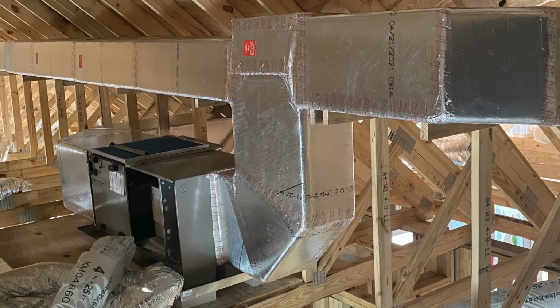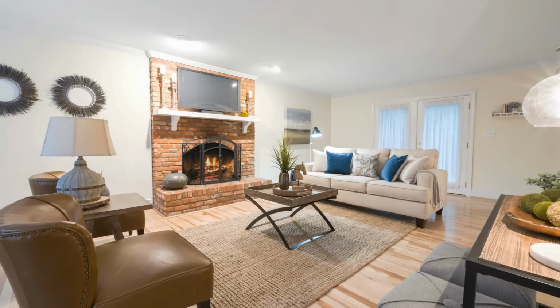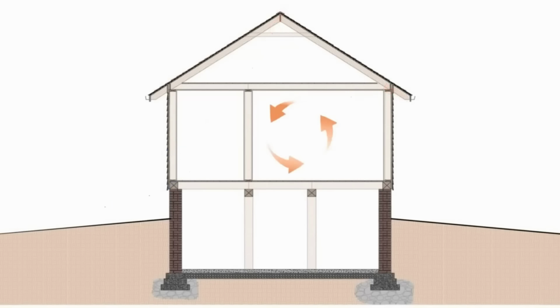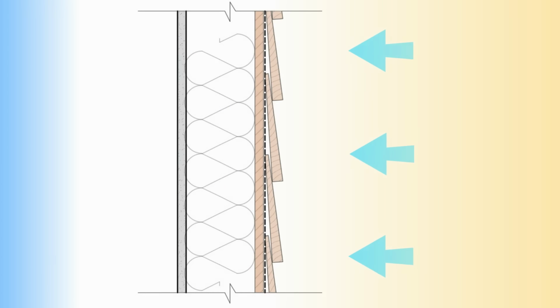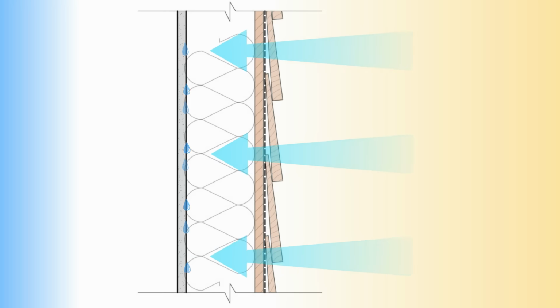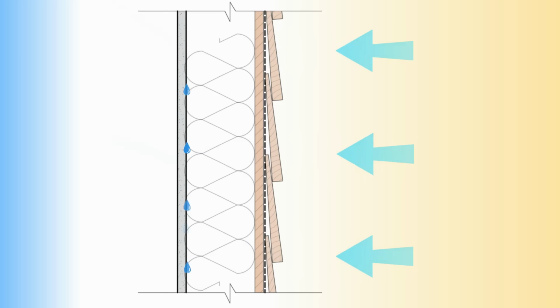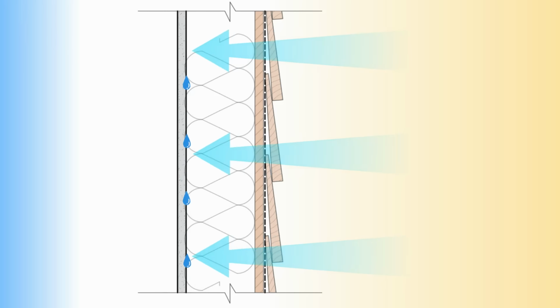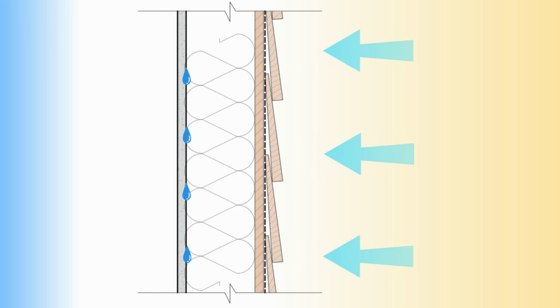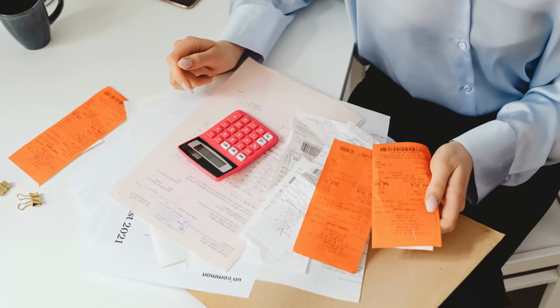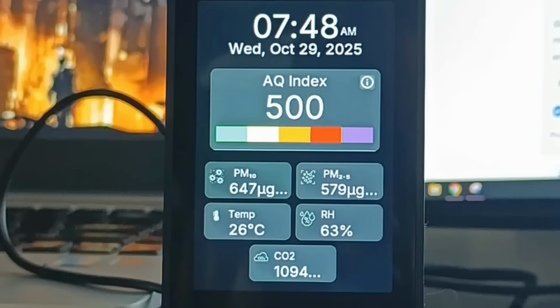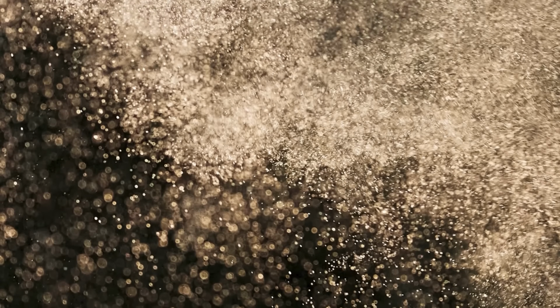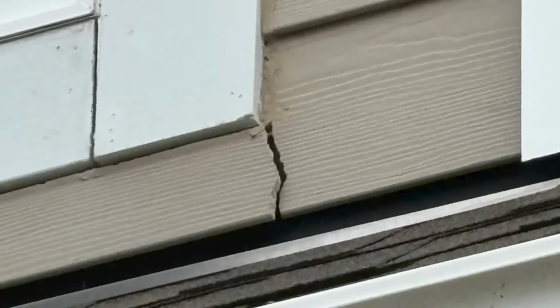Even worse, if your ducts leak into the attic, they can depressurize the living space below. This creates negative pressure inside the home, turning your house into a vacuum. Humid outdoor air can be sucked in through any tiny crack, poorly sealed electrical outlets, or windows to reach equilibrium. In warm climates, this constant inward drawing of humid air hits the backside of your interior drywall, which is kept cold by your air conditioning, resulting in hidden interstitial condensation and systemic mold growth within the walls. In cold climates, this results in high energy bills and poor indoor air quality from dust particles and other air contaminants being sucked into the building through cracks in the building envelope.